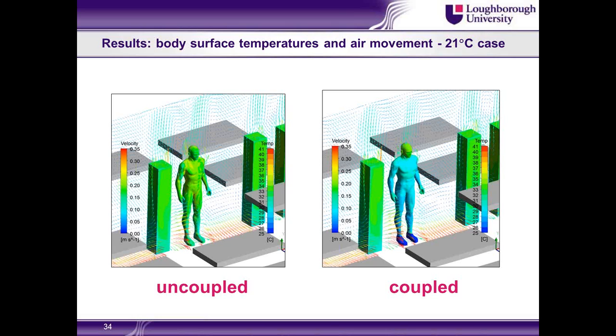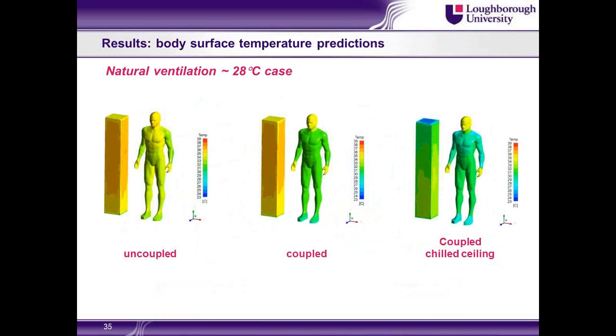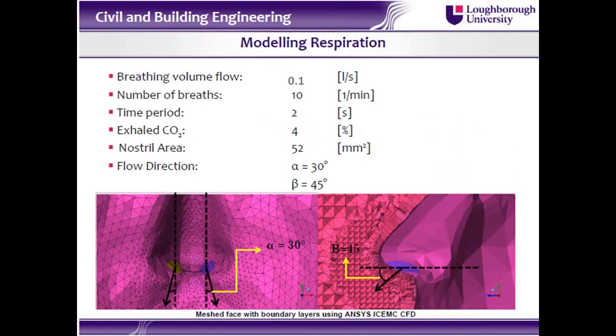And we're seeing interesting things like fresh air flowing in around the feet. So this is a naturally ventilated classroom, sorry. So fresh air is coming in at low level, washing around the feet. We're seeing some effect of that cooling around the feet at that point. The paper I'm presenting next week at ASHRAE is looking at the application of this model to chilled ceilings. So again, here's the uncoupled version, the coupled version, and then on the right-hand side here, we've got the coupled tool with the chilled ceiling. So we can see the effect of that on the torso as that body is facing the chilled ceiling.